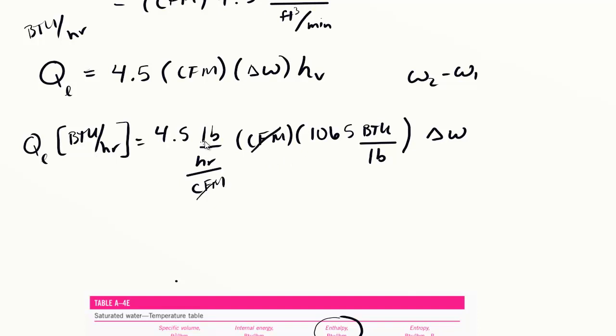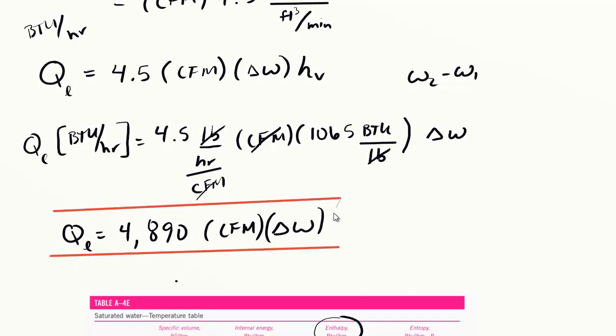What we get out is BTU per hour. The CFM cancels, the pound cancels, and the absolute humidity ratio is unitless. Our final formula is around 4,890 multiplied by your cubic feet per minute of air multiplied by your difference in absolute humidity ratio. That is our shorthand formula for latent heat processes, which will serve you well in your endeavors as an HVAC engineer. Hope to see you in the next videos.